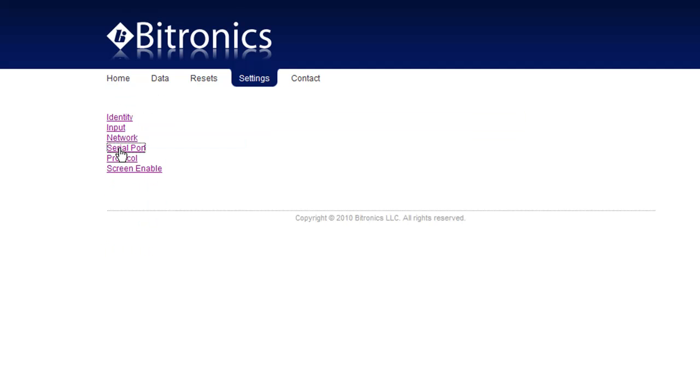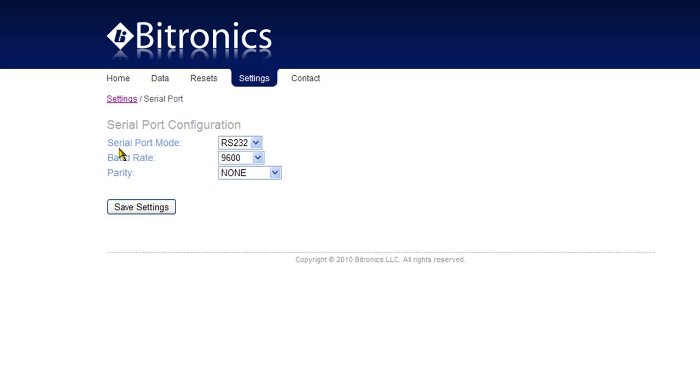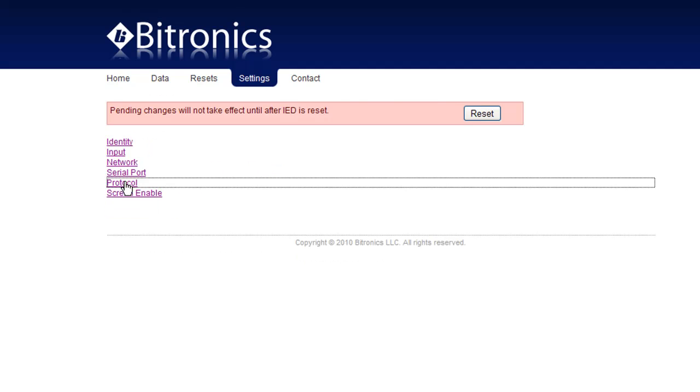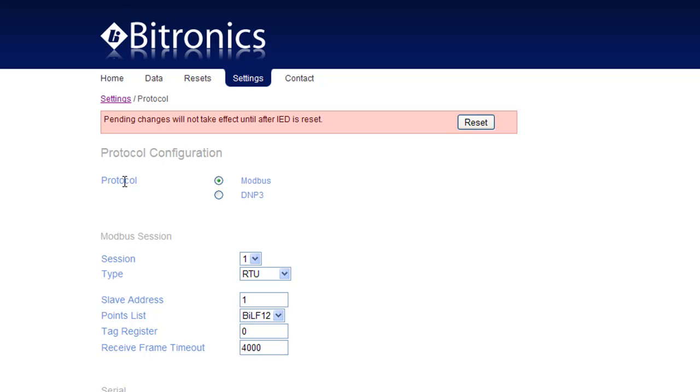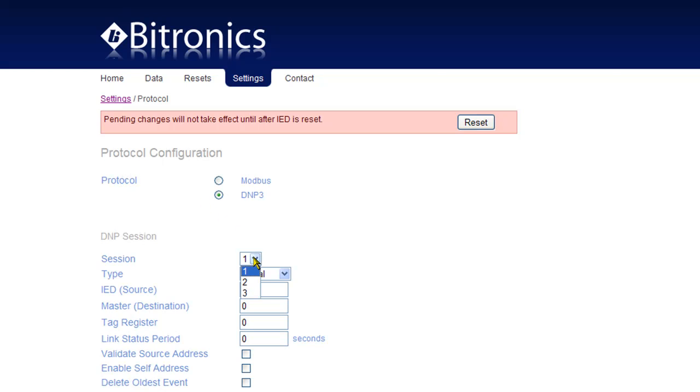Most conventional SCADA systems require a serial interface. Here's where the physical port configuration can be done. The M650 supports either Modbus or DNP and will service up to three completely independent sessions.